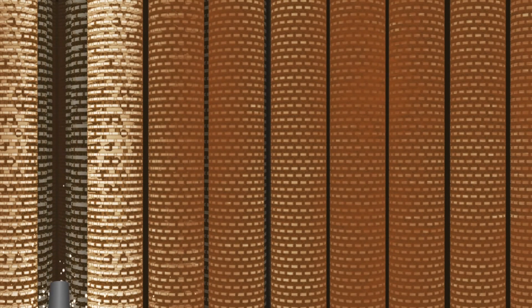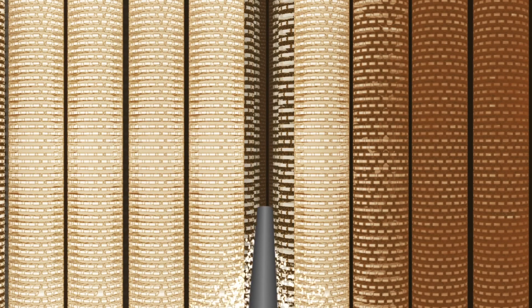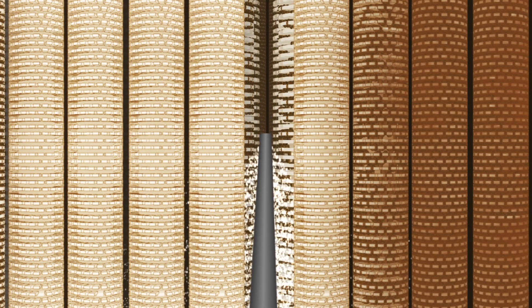In our proprietary process, a certified expert inserts a cleaning alignment tool between the tubes, spreading them and revealing an access lane deep into the module. Tooling is designed to go two tubes beyond the center point of the module, ensuring that every bit of the heating surface is cleaned.